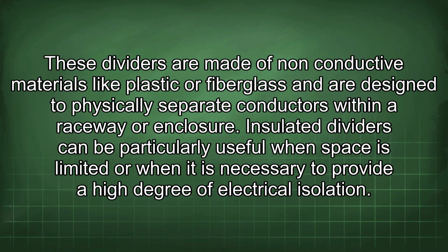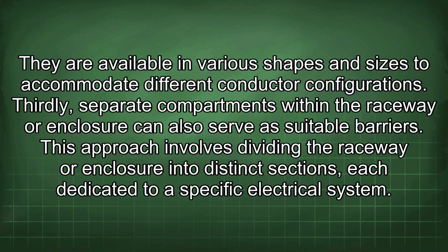Secondly, insulated dividers are another type of suitable barrier. These dividers are made of non-conductive materials like plastic or fiberglass and are designed to physically separate conductors within a raceway or enclosure. Insulated dividers can be particularly useful when space is limited or when it is necessary to provide a high degree of electrical isolation. They are available in various shapes and sizes to accommodate different conductor configurations.